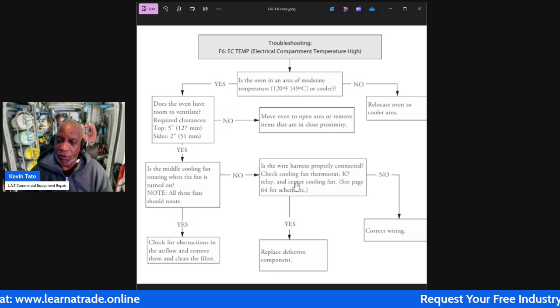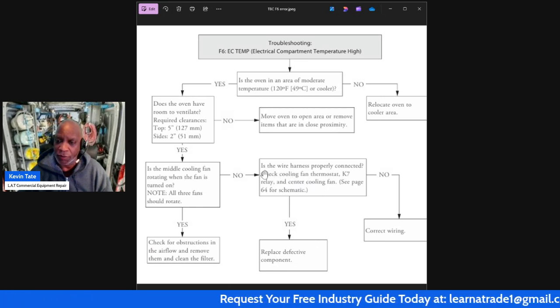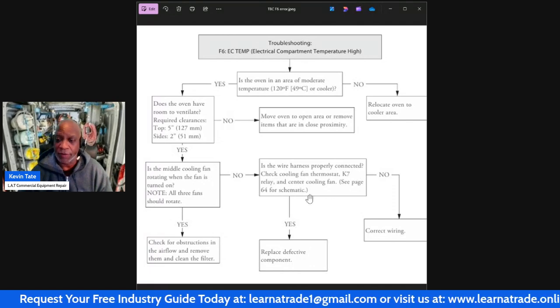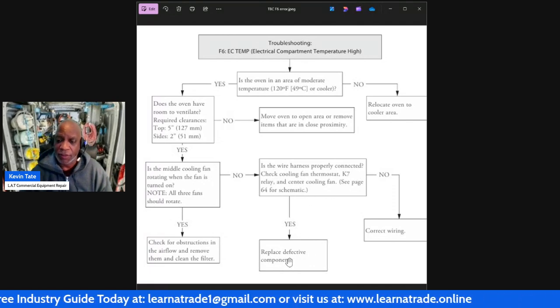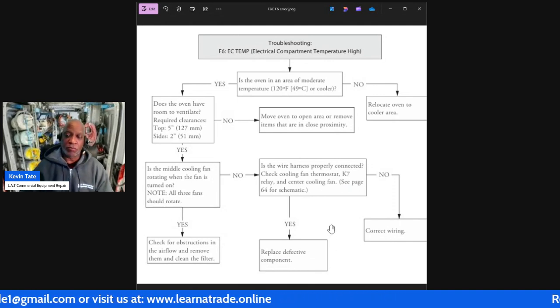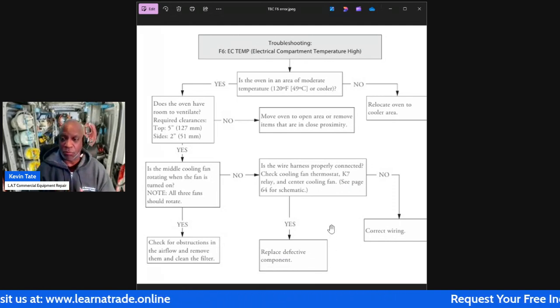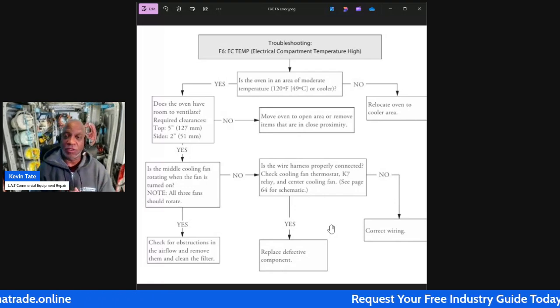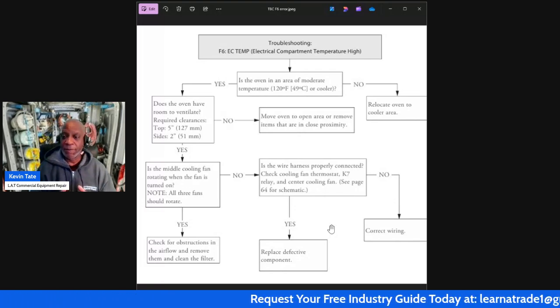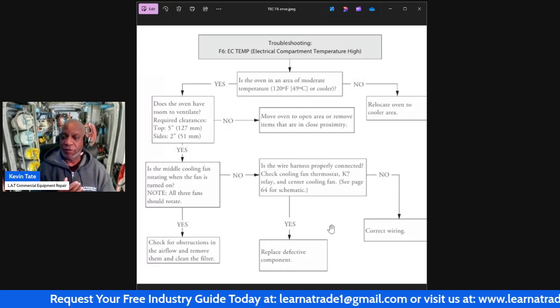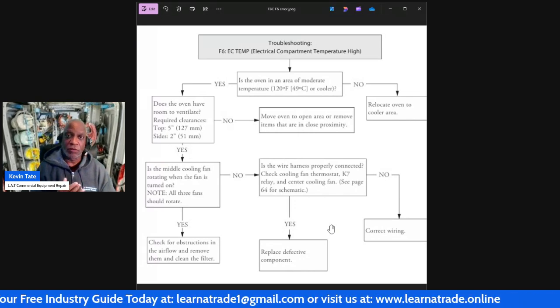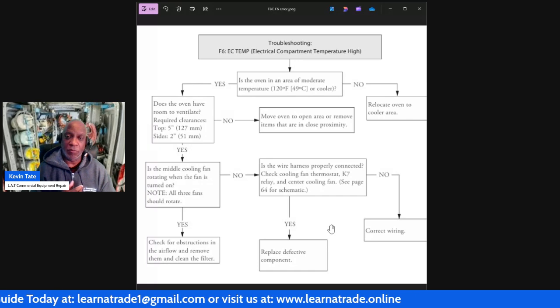Then in the middle part of the flow chart, it asks: is the wire harness properly connected? If yes, then it says replace the defective component. So that's saying if everything's plugged in right and checks out okay, then it's possible that fan could be bad.